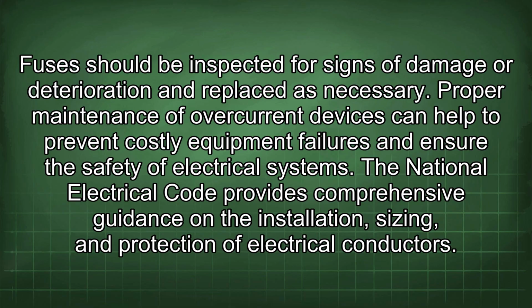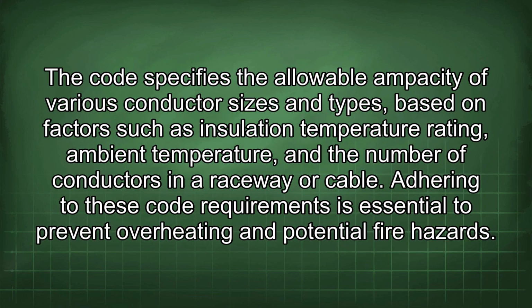The National Electrical Code provides comprehensive guidance on the installation, sizing, and protection of electrical conductors. The code specifies the allowable ampacity of various conductor sizes and types, based on factors such as insulation temperature rating, ambient temperature, and the number of conductors in a raceway or cable. Adhering to these code requirements is essential to prevent overheating and potential fire hazards.